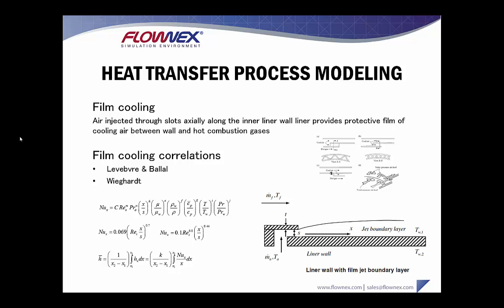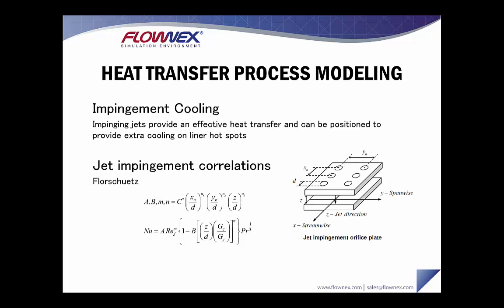Film cooling is air injected through slots along the inner liner wall, providing a protective film of cooling air between the wall and the hot combustion gases. This is a critical cooling mechanism that needs to be simulated within your network, and it can be represented using several well-known correlations implemented in Flownex. Any user-defined function or correlation can also be quite easily implemented. Impingement cooling is where jets provide an effective means of heat transfer and can be positioned to provide extra cooling on liner hot spots. The jet impingement correlation implemented in Flownex is pretty standard within the gas turbine industry.